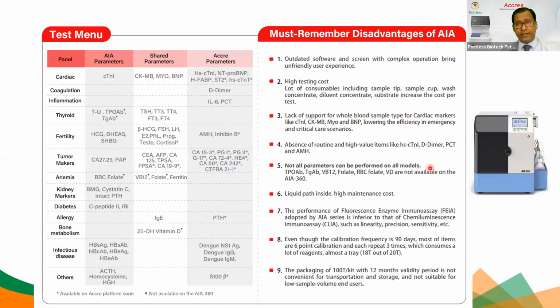So the calibration frequency is less in AIA 360, but the problem is that you have to do multi-point calibration, 6-point calibration with 3 times repeat. So around 18 tests. They have a smaller pack size of 20 tests, but again, 18 tests are used for calibration. Only 2 tests are for the test. It's not possible as a real protocol. So these are the problems.